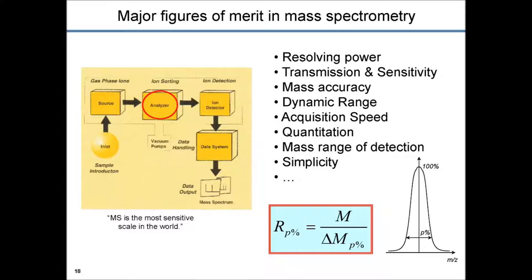Even though a modern mass spectrometer looks a little more complicated than 100 years ago, we still see the same three major building blocks: source, analyzer, and ion detector, but we also have a data system for data processing. The analyzer is still the heart of the mass spectrometer. An analyzer is characterized by a number of key analytical figures of merit: first of course is resolving power, but then transmission which turns into sensitivity, mass accuracy, dynamic range, acquisition speed, quantitation capability, mass range of detection, and last but not least, simplicity.